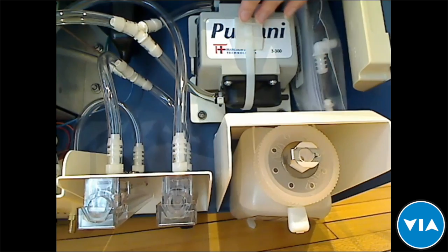We have here the air pump, and this is a small air compressor. It's designed to be run for years at a time. It's a type of diaphragm pump, so it only has these two rubber pieces that oscillate back and forth. So there are no metal pieces moving back and forth, which allow it to run for a very long period of time. We have tubing that connects from the pump to the flow meters and out to the baby.